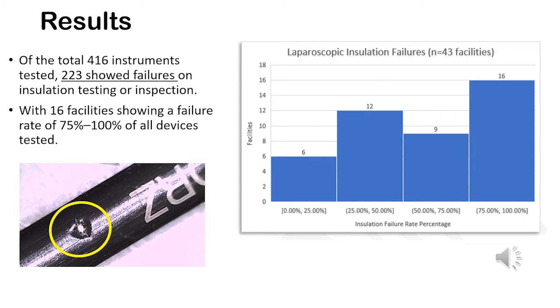So let's go right to the results. Of the 416 instruments tested, 223 showed failures on insulation testing or even inspection, as noted here on the graph, with 16 facilities showing a failure rate of 75% to 100% of all devices tested.